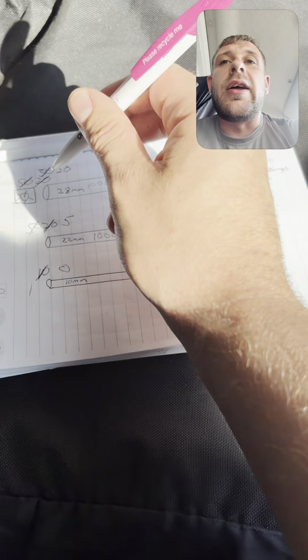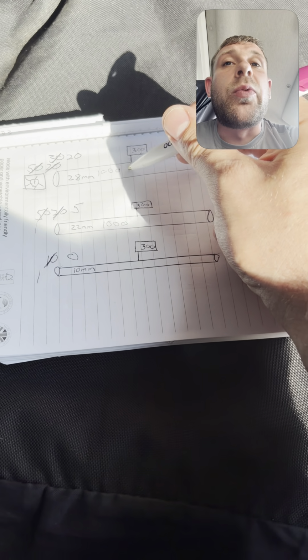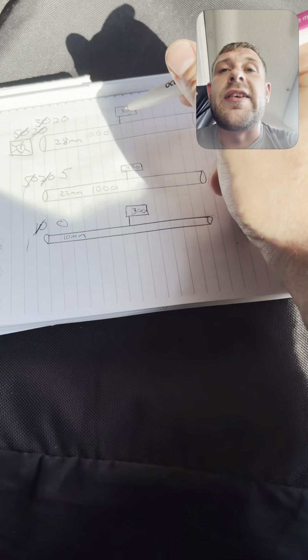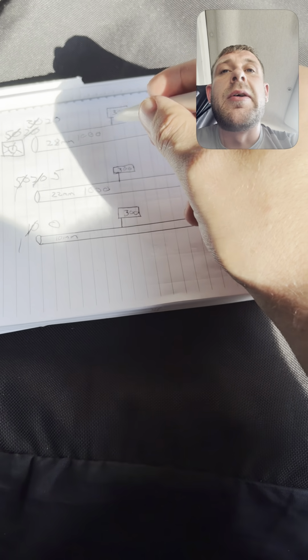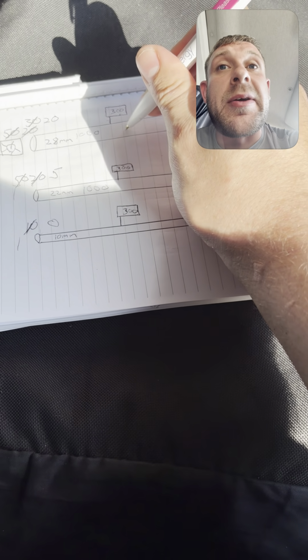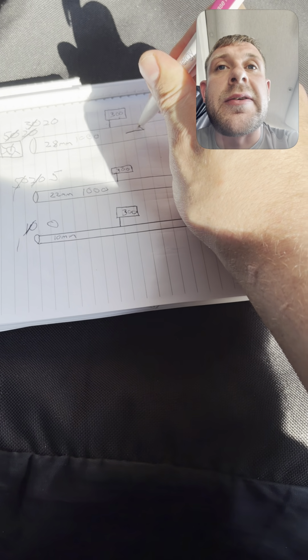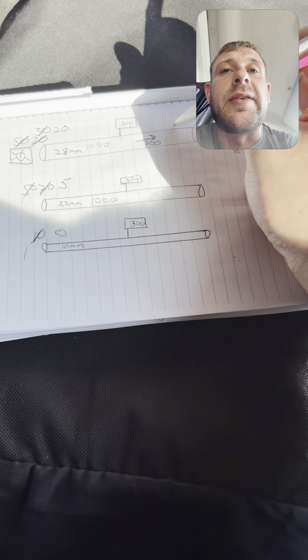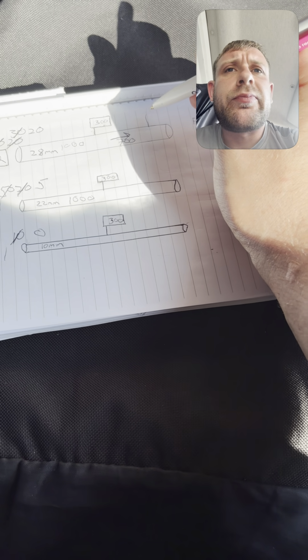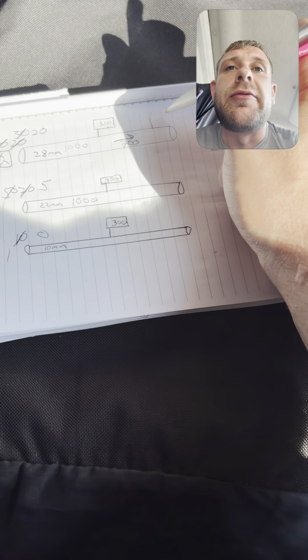Once it's gone around this first radiator, this bit of pipe was carrying the 1000 litres per hour, but now we've run through this radiator that was 300 litres per hour. Now this bit of pipe is carrying the rest of the system, which is 700 litres per hour. And then further up this system, you might have one radiator that needs 500 litres per hour, and you might have one that needs 200 litres.